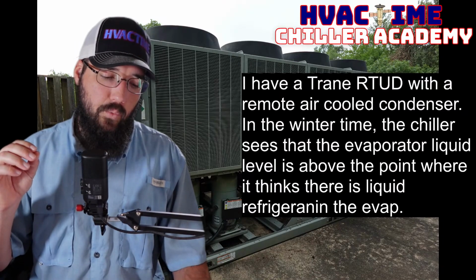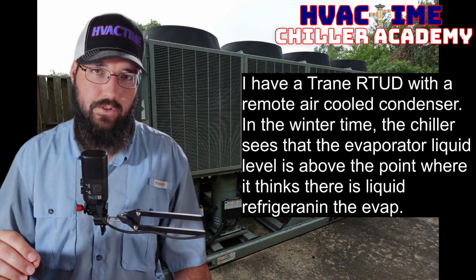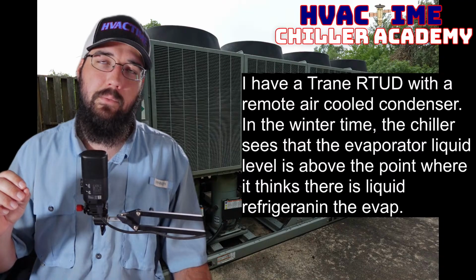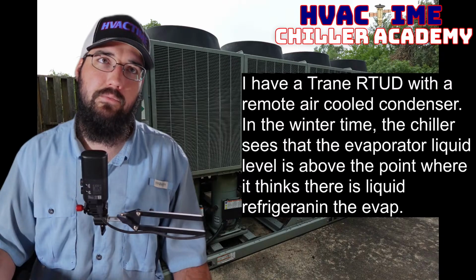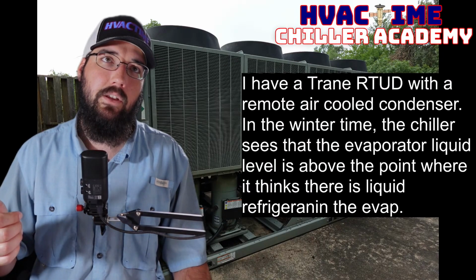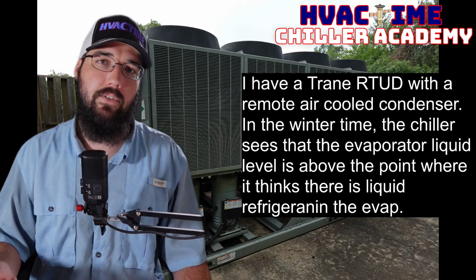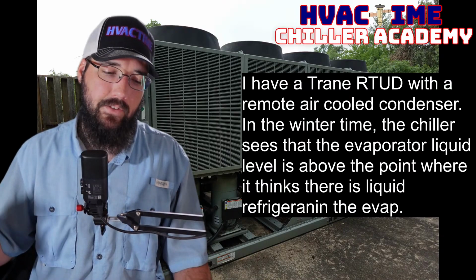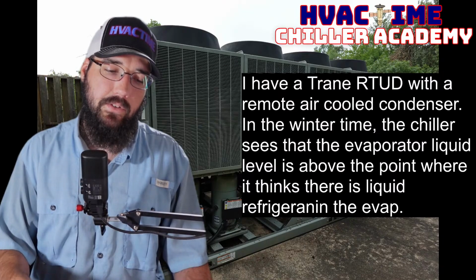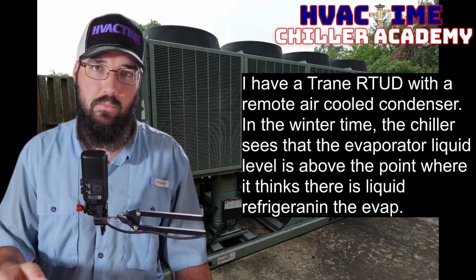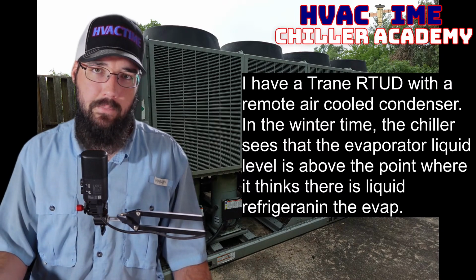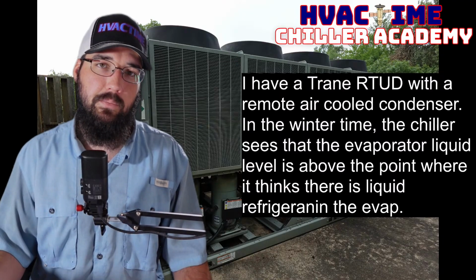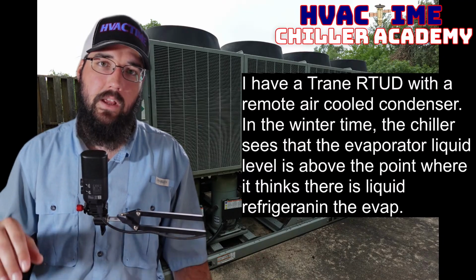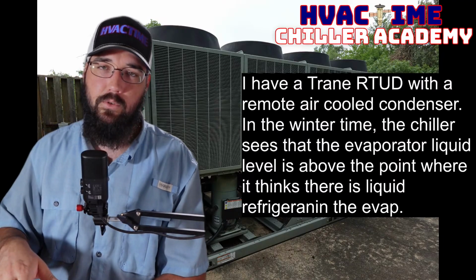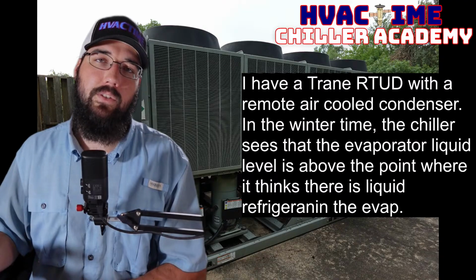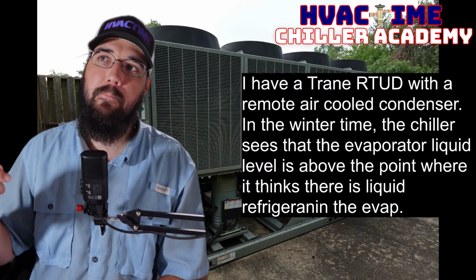Is that check valve having an issue? I think one of the keys here is you have a low ambient condition. And if memory serves, you're going to have condenser fans that cycle based off of saturation, but I think there should also be a pressure regulating valve on the bypass, sending hot gas to the liquid line. If I'm not mistaken, that should also be part of that remote condenser assembly, more than just condenser fan control, because if you get into a really low ambient condition, even with the fans off, you can still end up in a spot where the saturation is dropping too much, or the pressure is dropping too much on the liquid. Part of what that's going to do is reduce your velocity through the system.